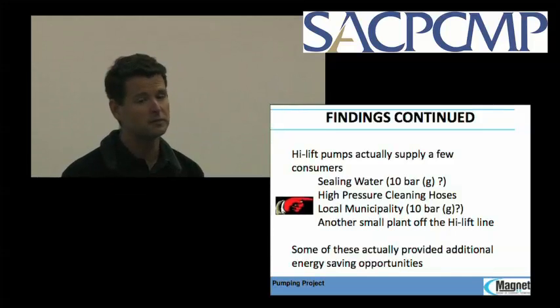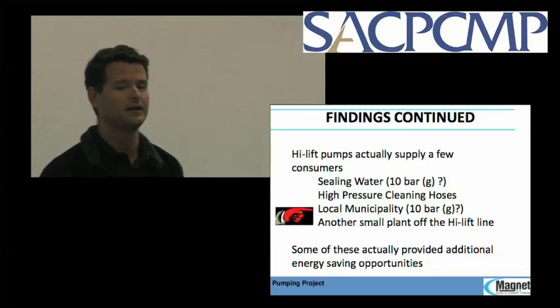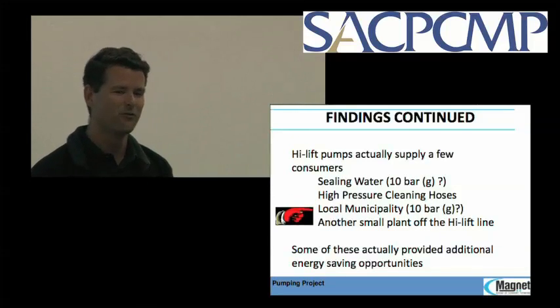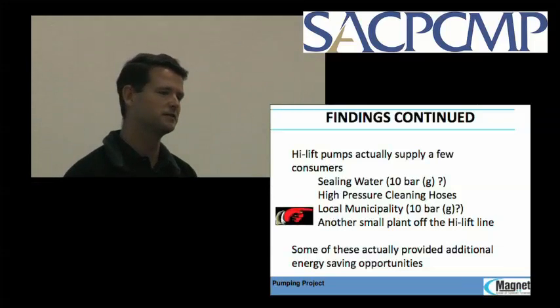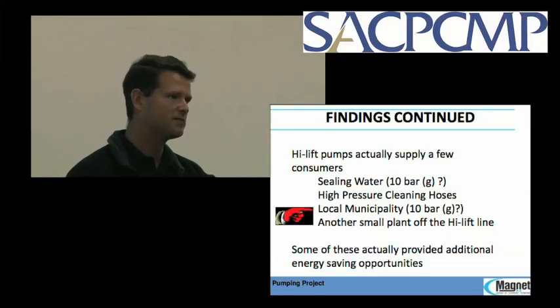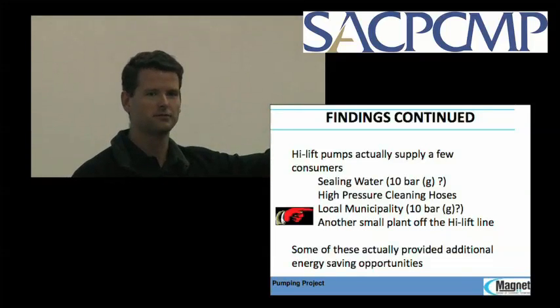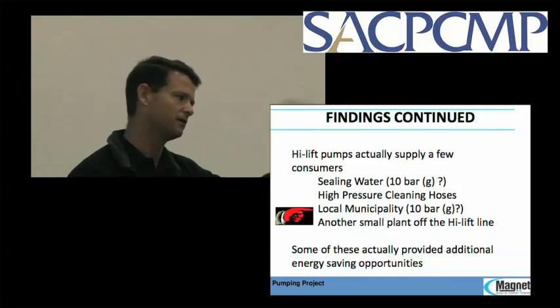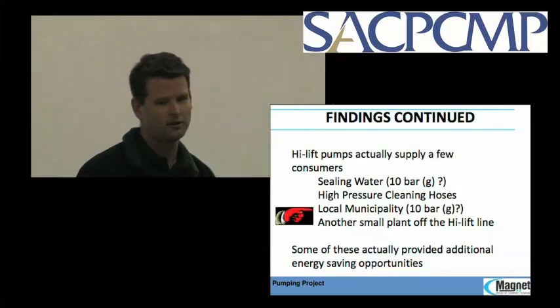They also supplied the local municipality with 10 bar water. And when I say the local municipality, this is like a little water processing station that then pumped across the river, and it was situated about 5 meters above the plant next to it. So you've got 100 meter head water supplying a back pressure of half a bar.